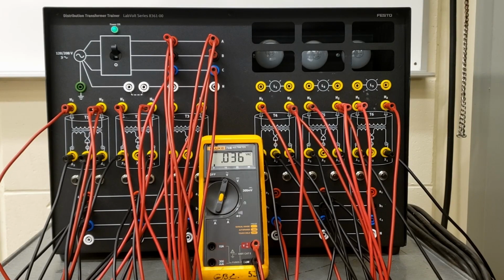Considering that the two transformer banks are identical, the voltage between the corresponding lines of the transformer bank is approximately 0 volts, so one can assume there is no phase shift between the corresponding lines of each transformer bank. Turn off the distribution transformer, leave the configuration connected to T1, T2, T3 so as to compare it with the next configuration, and disconnect the delta-delta zero phase shift configuration on T4, T5, T6.